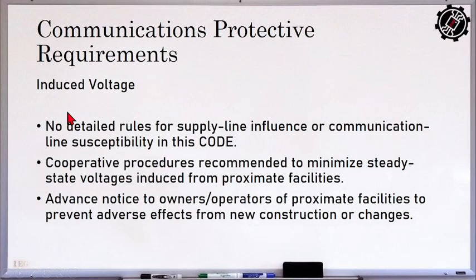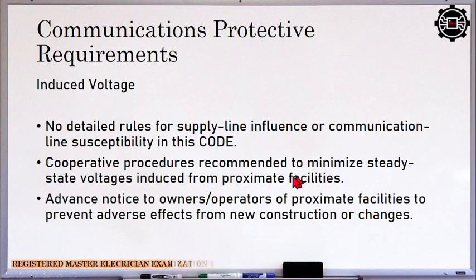Okay, so if there is a high induced voltage, there is no detailed rule for supply line influence or communication-line susceptibility for induced voltage. What is recommended is to follow procedures to minimize steady state voltage induced from proximate facilities. The procedures will be formed by the distribution utility company. Then advance notice will also be given to the operators of proximate facilities to prevent adverse effects from new constructions or changes.